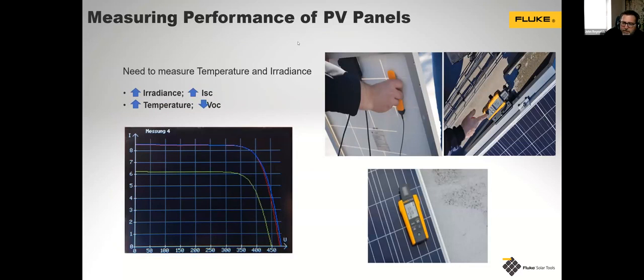So when we're measuring the performance of the panels using an irradiance meter, there's several things that we need to take into account. Obviously, we've got the irradiance and the temperature, and for that, we're going to be using the Fluke irradiance meter. But one thing that we will notice is that the bottom photo is not best practice. We're not looking to actually put the product on the panel itself. There may be situations where you have to, but if you do so, you need to be very careful because there's a risk of damaging the panel itself.